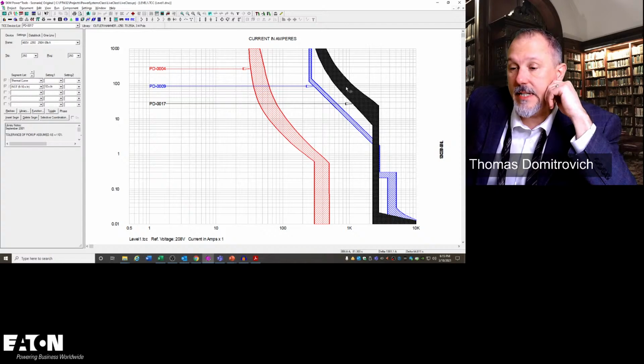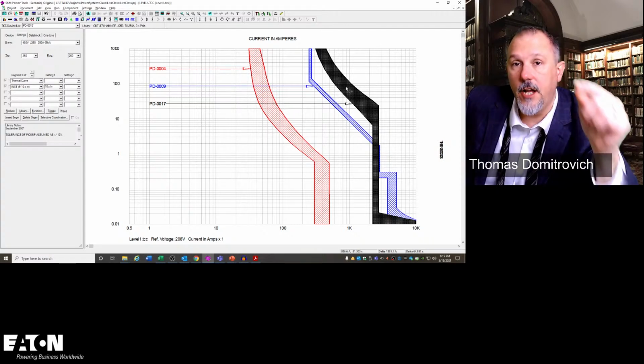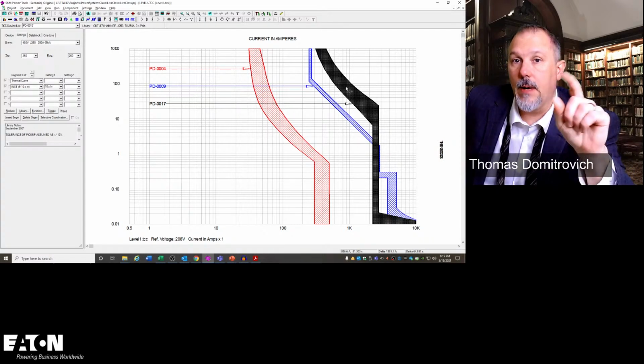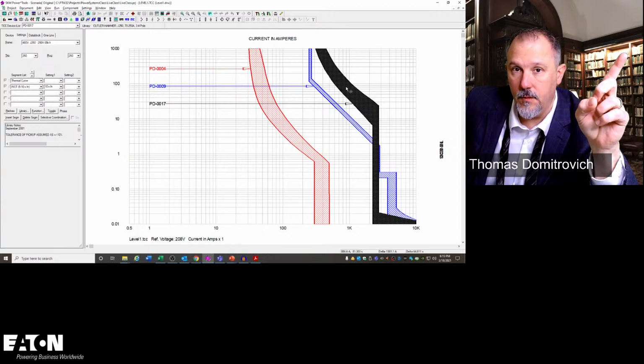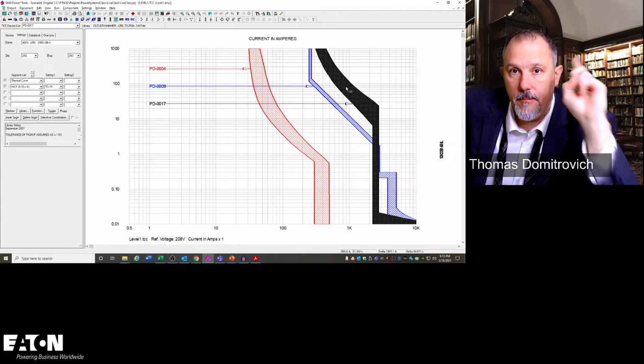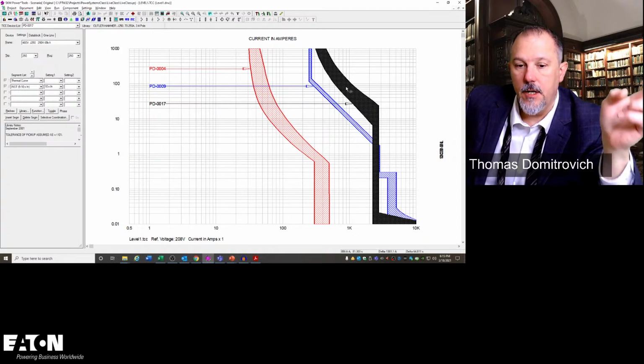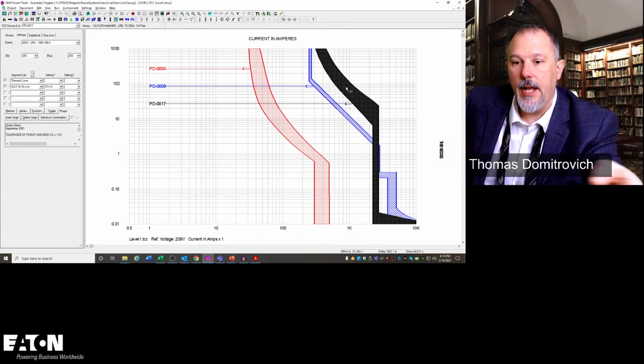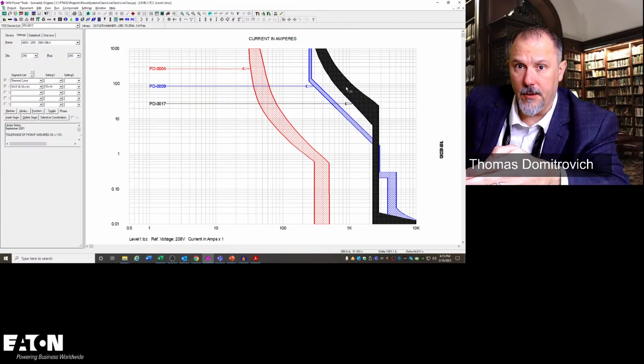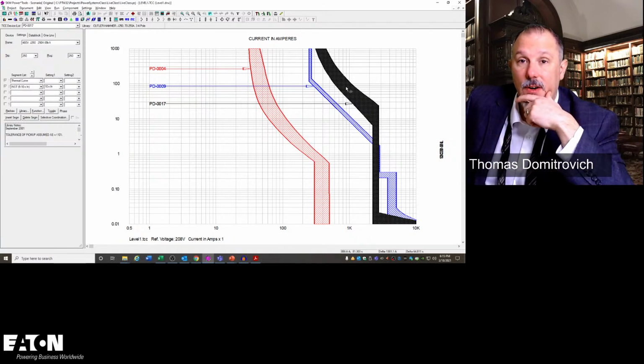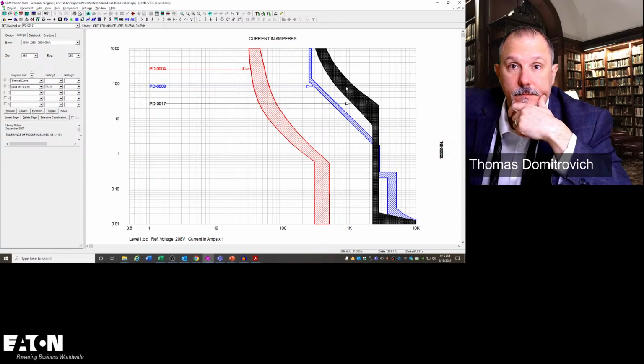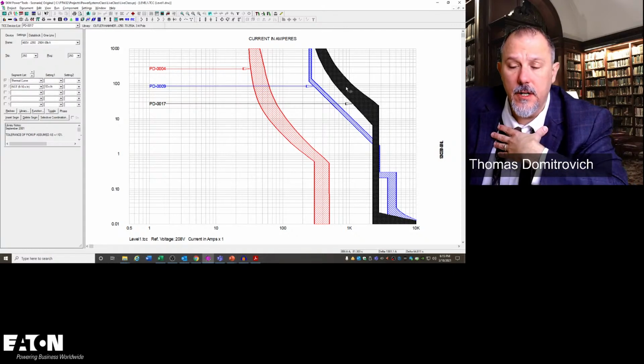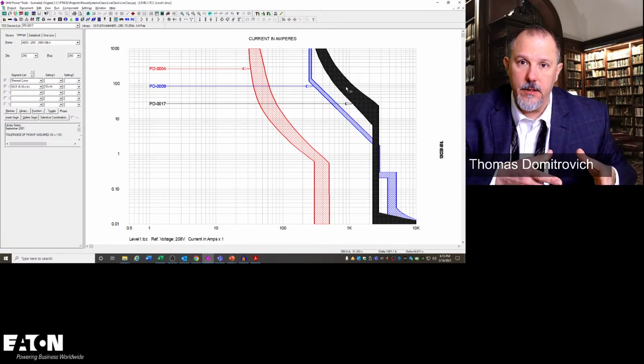There, he calls me one day and he says, the jail just went down. And what happened was there was a fault on the roof. It took out the main for the facility. The transfer switch transferred over to the generator. And then the generator breaker tripped. And he says, Thomas, why did that happen? Now, it wasn't our breakers, but he wanted to understand why it happened.